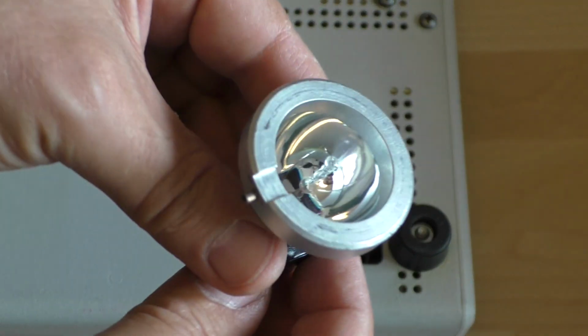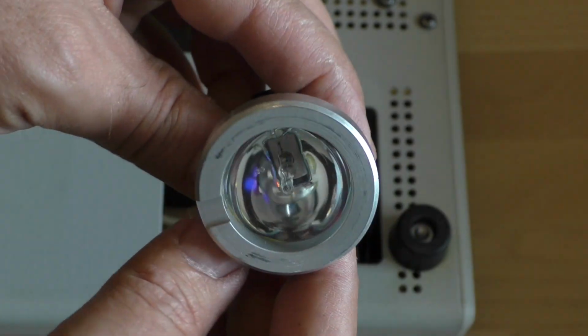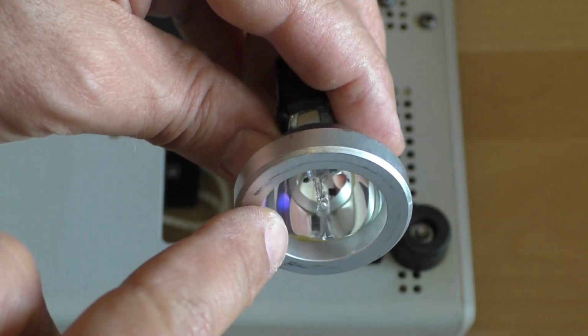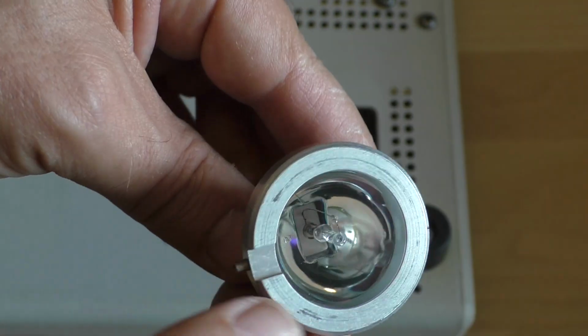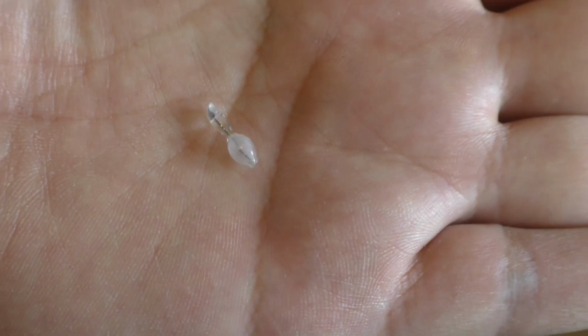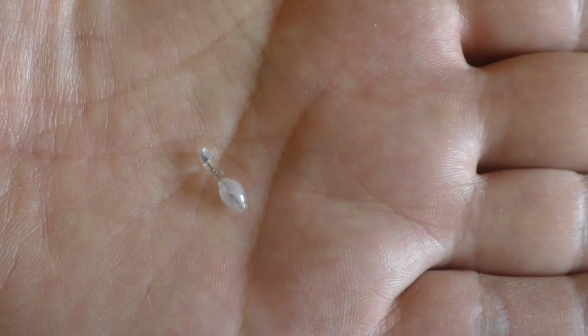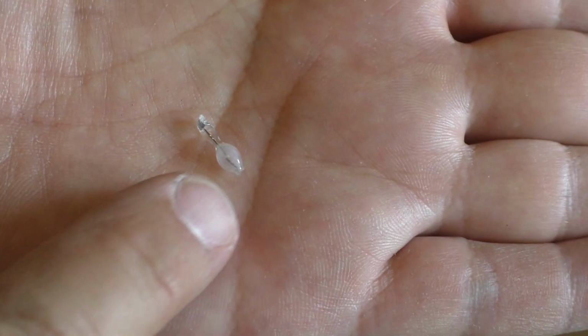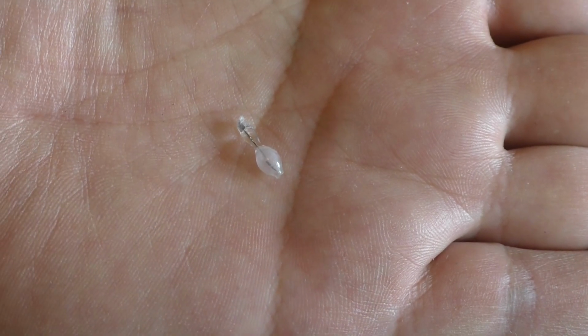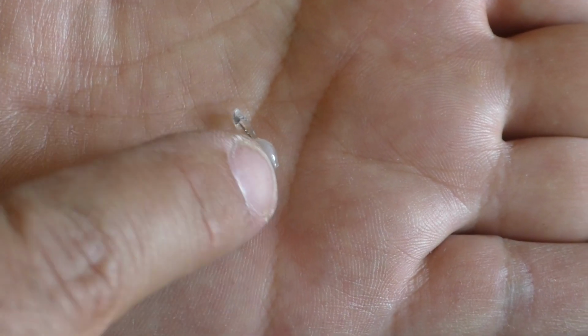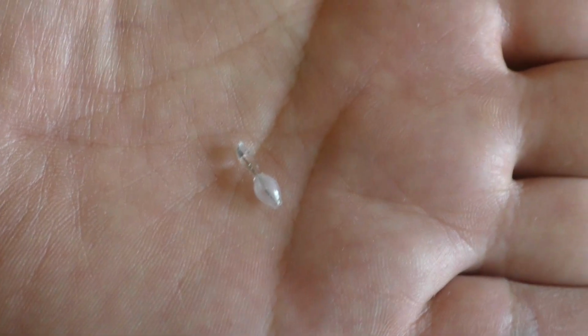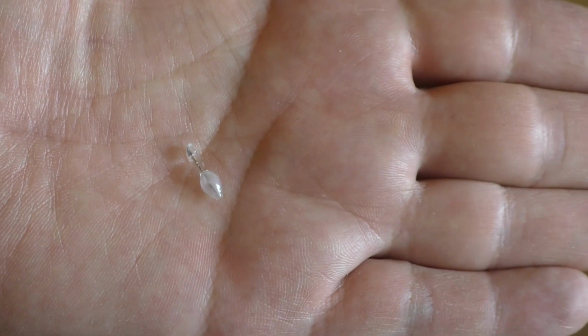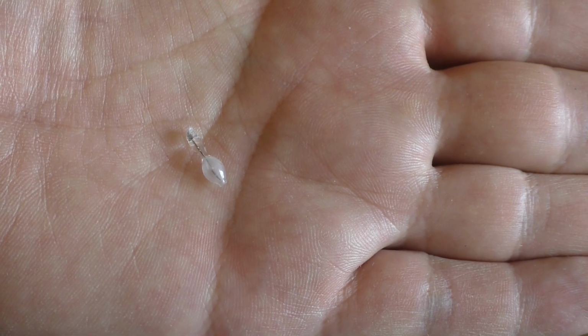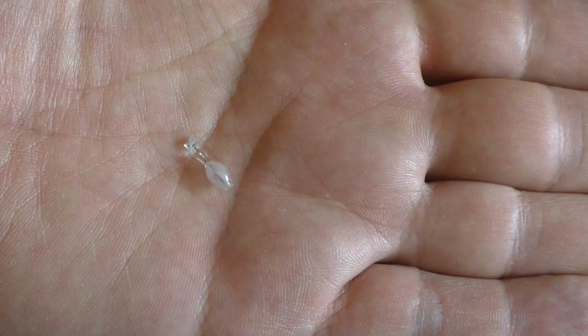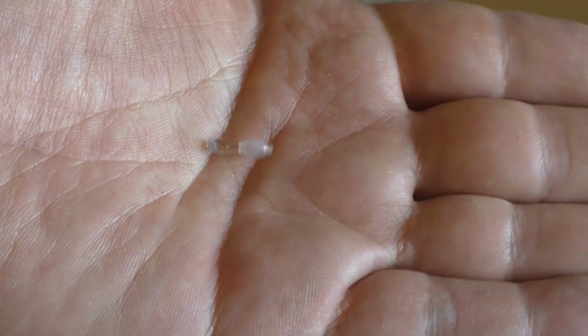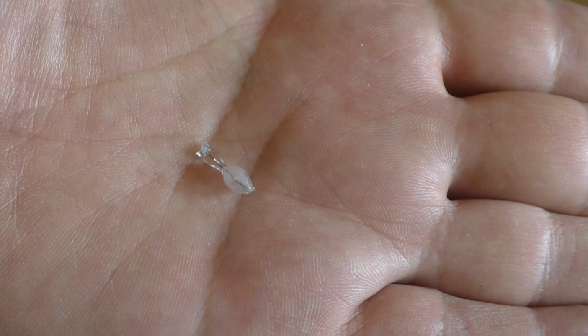Yes, so that's the bulb with this tiny little xenon burner inside. And that is the actual lamp here, this tiny little bulb with one contact here. The other contact on the other side is broken off. So this was inside the case. I suspect that one of the earlier lamps exploded and that fragment was left inside the device.